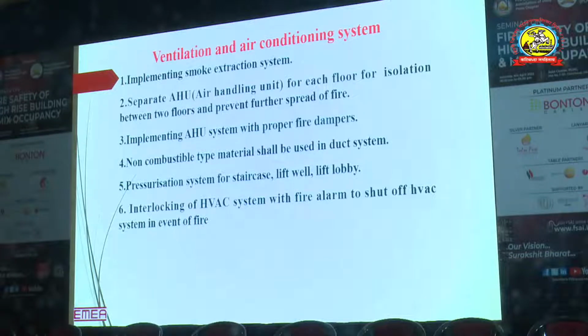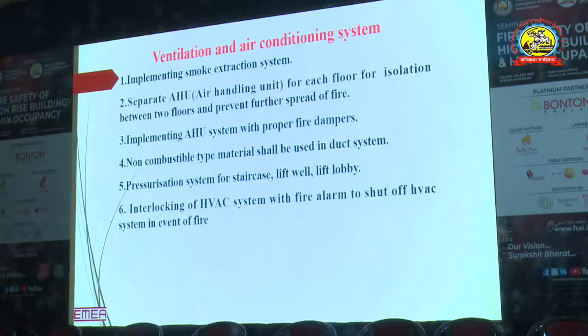Non-combustible material shall be used in the system. In most places this point is also not taken care of properly by the HVAC contractor. So non-combustible material must be used in the HVAC duct system. A pressurization system for staircase, lift well and lift lobby is a must. It is one of the life safety equipment during a fire. The interlocking of the HVAC system with the fire alarm to shut off the HVAC system in the event of fire is also one of the important aspects in the ventilation of a high-rise building.